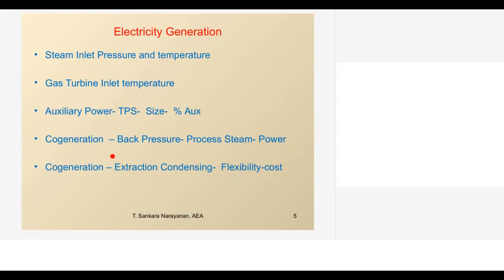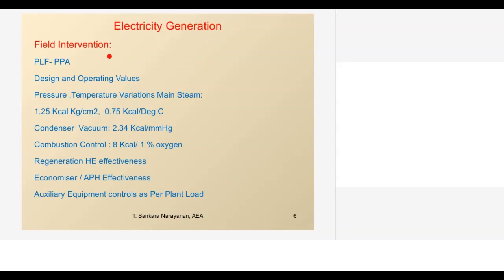Second, cogeneration. Many industries use cogeneration. Cogeneration, again a back pressure route, we get the maximum benefit because steam is used for the process and power is used within the plant. If surplus is there, it can be exported. Again, cogeneration has another configuration, extraction condensing. Whenever extraction condensing is there, it gives flexibility for the industry: whatever variation in steam load, accordingly they can run extraction and take more power through the condensing route. So with cogen extraction condensing, we need to review the operating cost. So these are all the field interventions, what can be done in a generation activity.